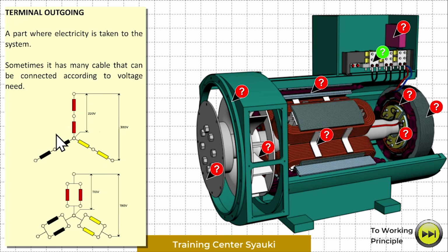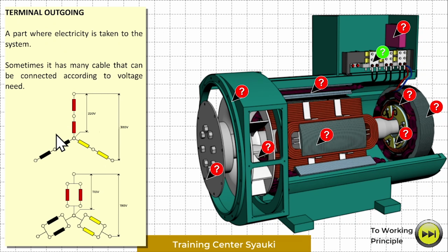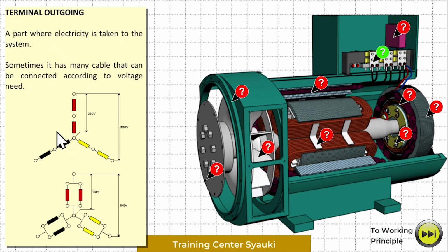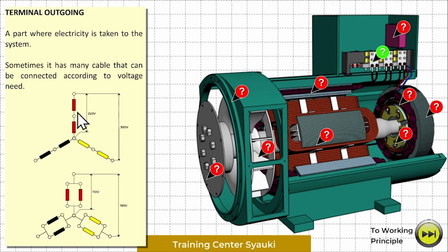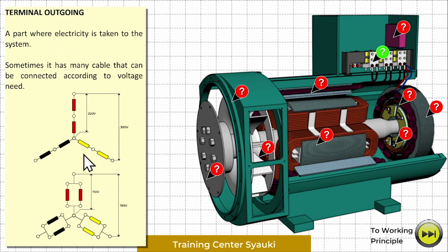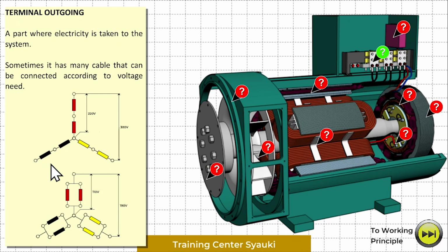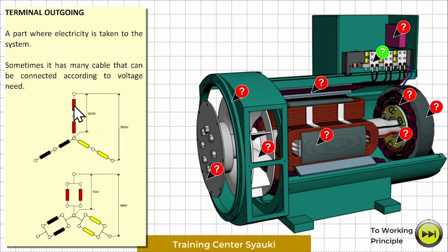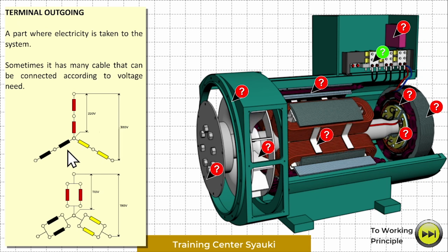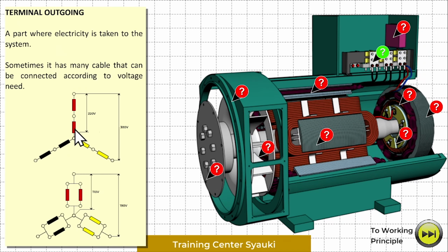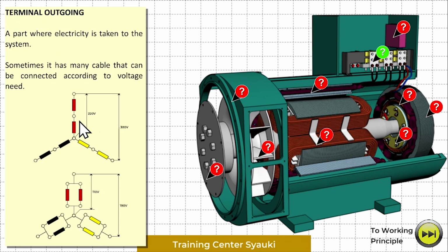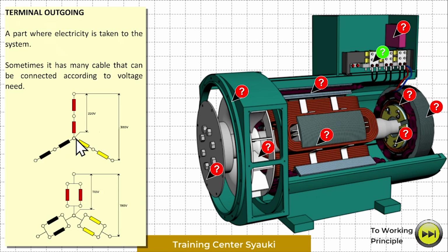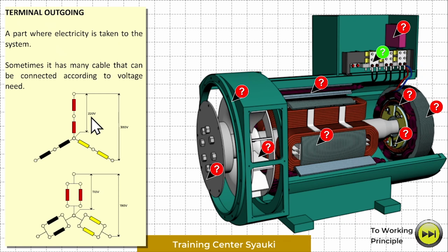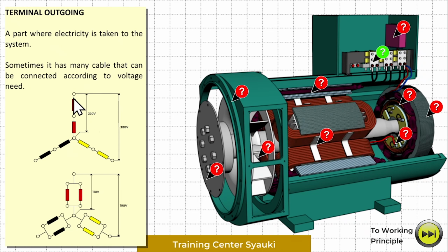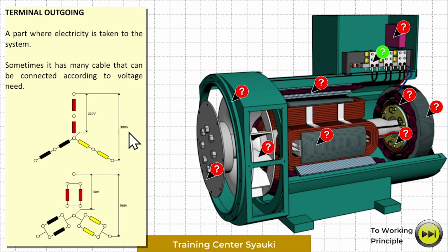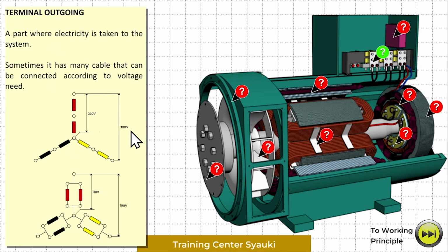For example, in a 3-phase generator, the stator has 6 windings, not 3. Two windings is line 1, two windings is line 2, and the rest is line 3. I'll mark these with red, yellow and black. If connected serially, the voltage phase to neutral is 220 volts. Phase to phase, it's 380 volts. This is an example from our country; in your country the amount may be different.